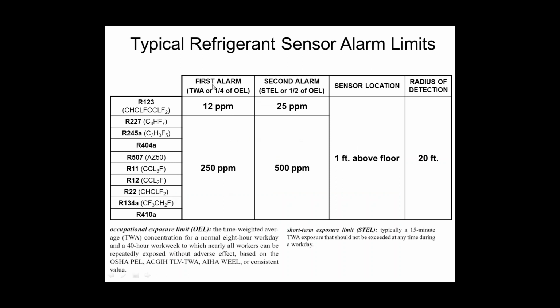These are the levels that we typically are looking at. The TWA number, also referred to as 1/4 of the OEL number, typically is 250 parts per million. If we get to 250 parts per million of nowadays 134A or 410A, or even the older refrigerants 22 or 12, I need to generate alarming. We typically have a secondary alarm. For this particular scenario, it's not going to really make a difference. I'm going to alarm at the 250, and hopefully everybody gets out of there. But we do have a secondary alarm for lots of gas detection systems, and typically it ends up being double the primary.